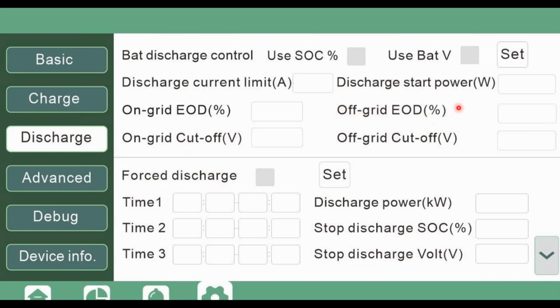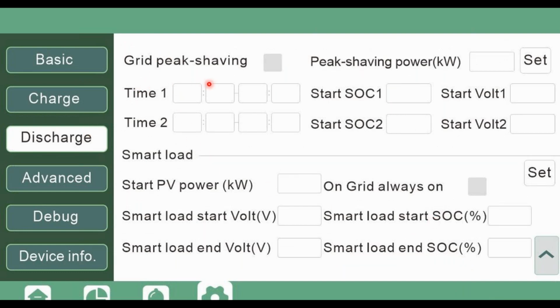On your off-grid here, if you have off-grid and you have a generator, we recommend setting this maybe 5 to 10% lower than your generator settings, so they don't intermingle. And then while enabling the forced discharge and using time of use settings, it will force discharge the battery into selling to the grid. You can limit the power by using the discharge power function and then stopping at the desired SOC. Now we have the grid peak shaving, to offset some of that power and help with demand response. You enable it and set your time of use, and then set how much power you want to shave out of the AC, right?